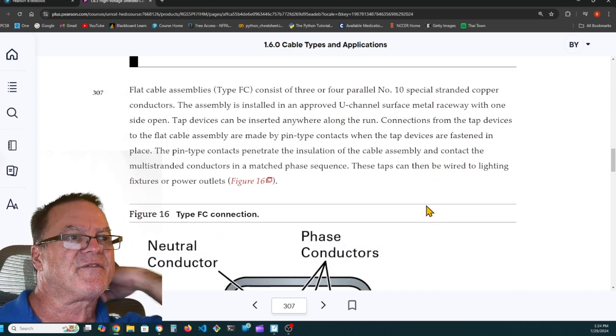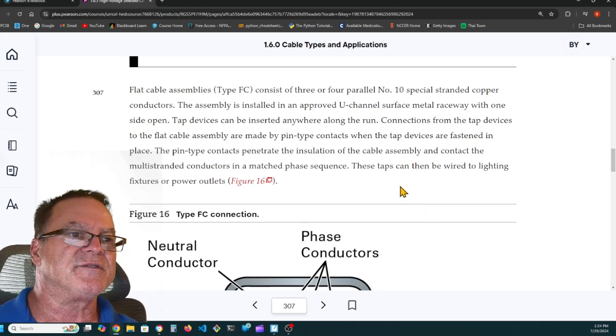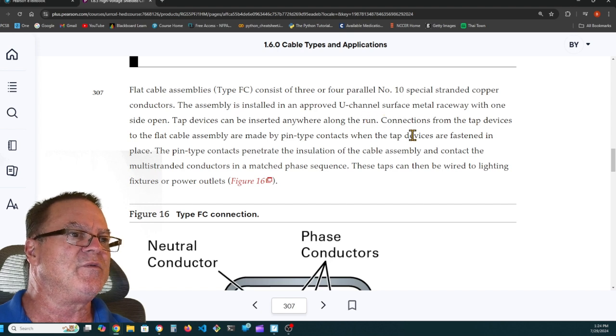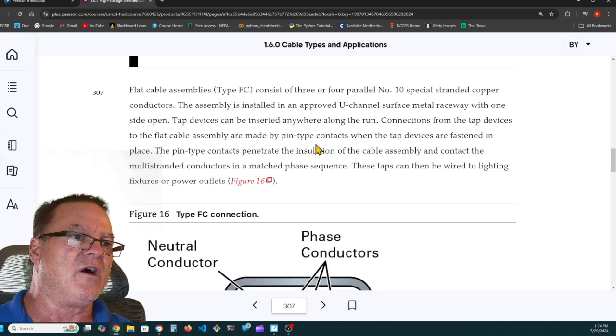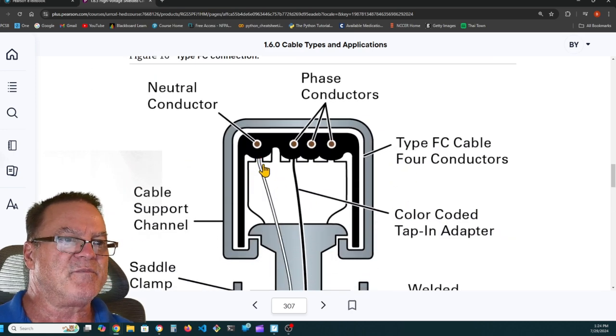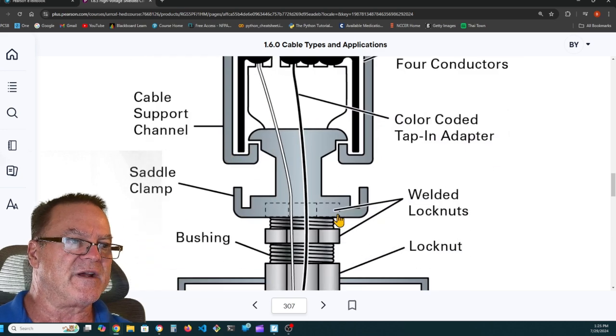Flat cable assemblies consist of 3 or 4 parallel number 10 special stranded copper conductors. The assemblies are installed in an approved U-channel surface metal raceway with one side open. Tap devices can be inserted anywhere along the run. Connections from the tap devices to the flat cable assembly are made by pin-type contacts when the tap devices are fastened in place. Pin-type contacts penetrate the insulation of the cable assembly and contact the multi-stranded conductors in the matched phase sequence. So these pins will tap into whichever ones of these they need. And these are 3 phases like A, B, C, maybe black, red, blue. And this is your neutral conductor. And then the very shell itself is the ground.